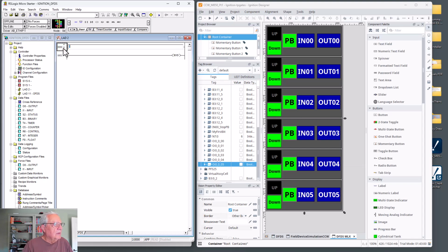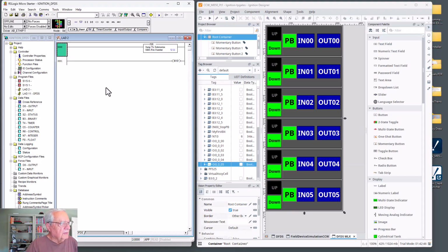Let's add that. Double click on it here and go to a text editor, JSR 11. When ladder 2, which is the only file that runs automatically in a MicroLogix, executes, the first thing it's going to do is go to ladder 11. Now remember that the scan rate or the refresh rate on this processor is better than 1,000 times a second. Any discrepancy of you operating these buttons over here and looking at the lights, you won't notice it.